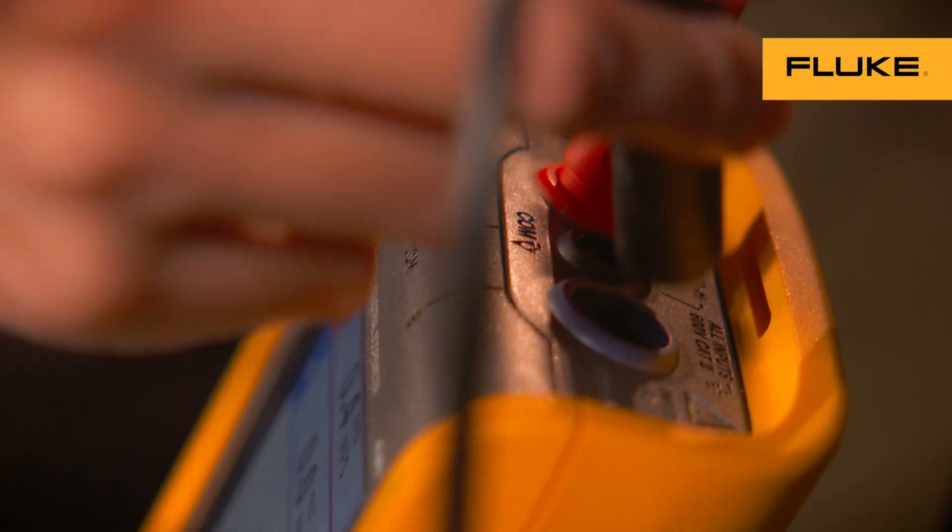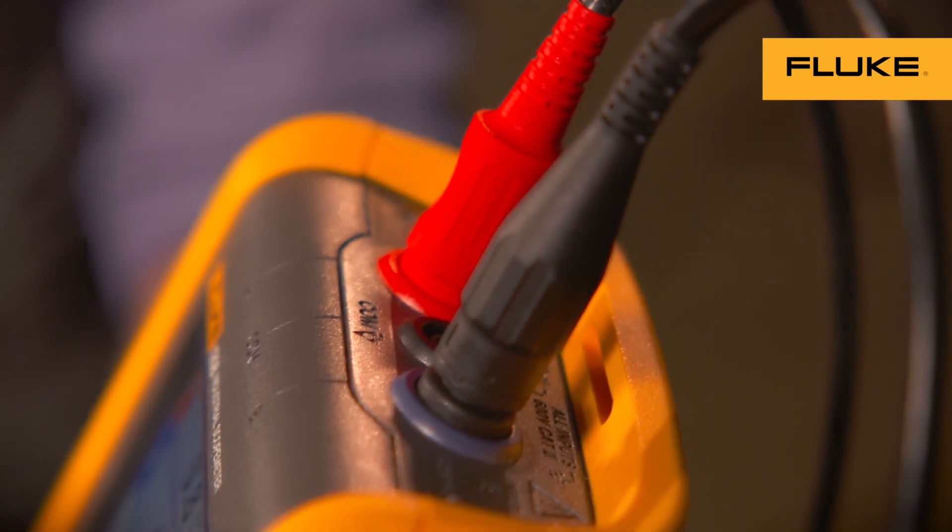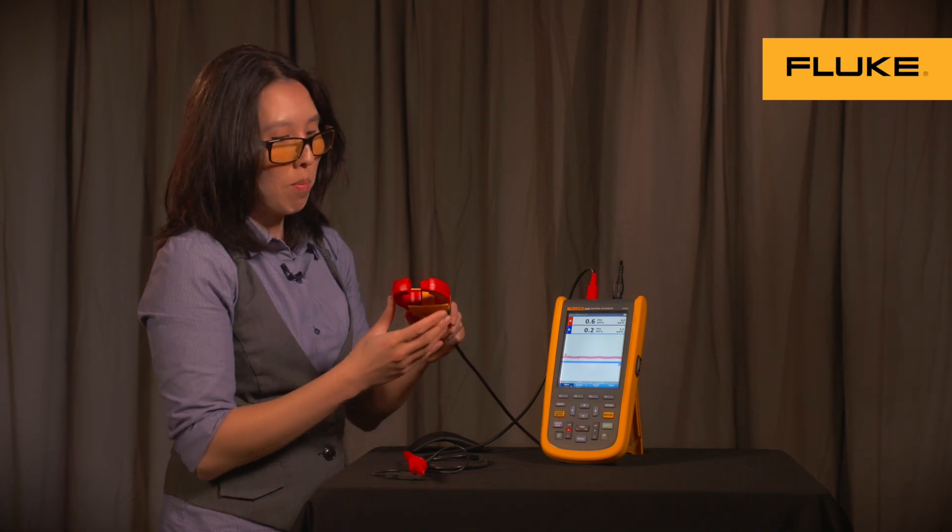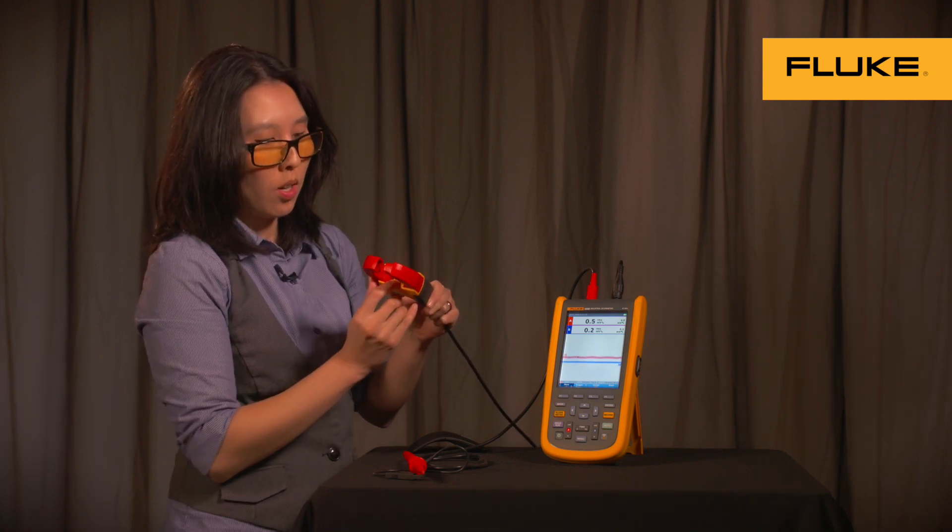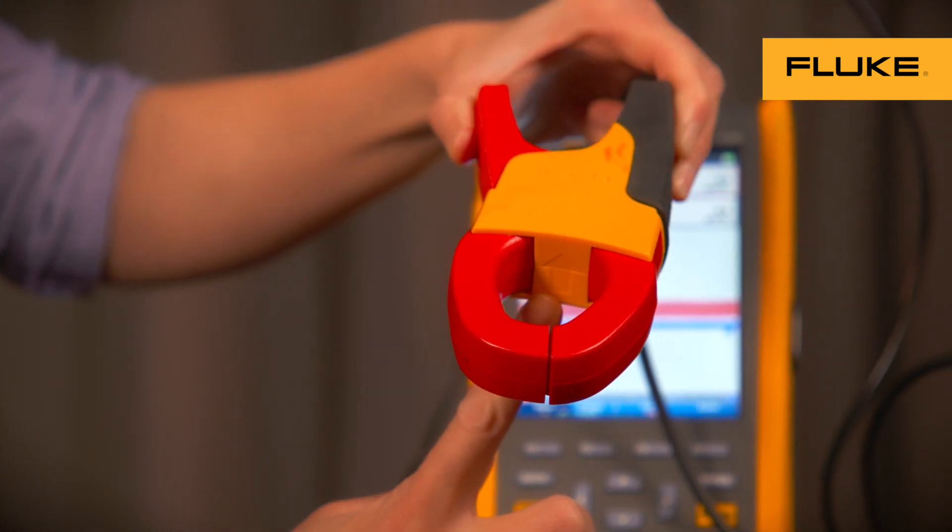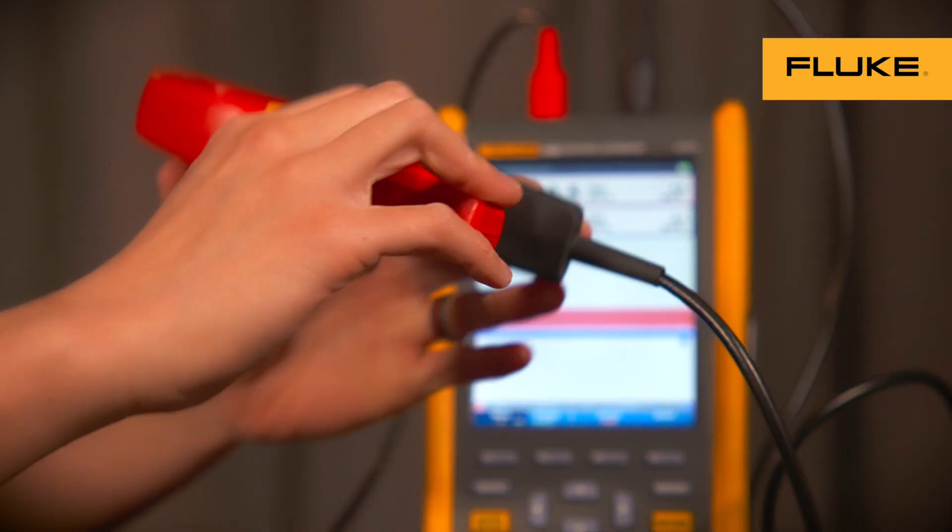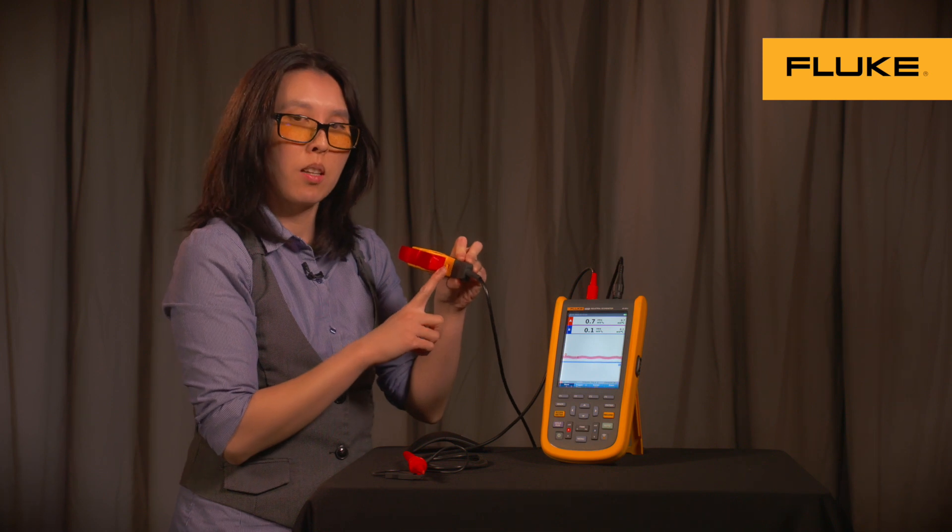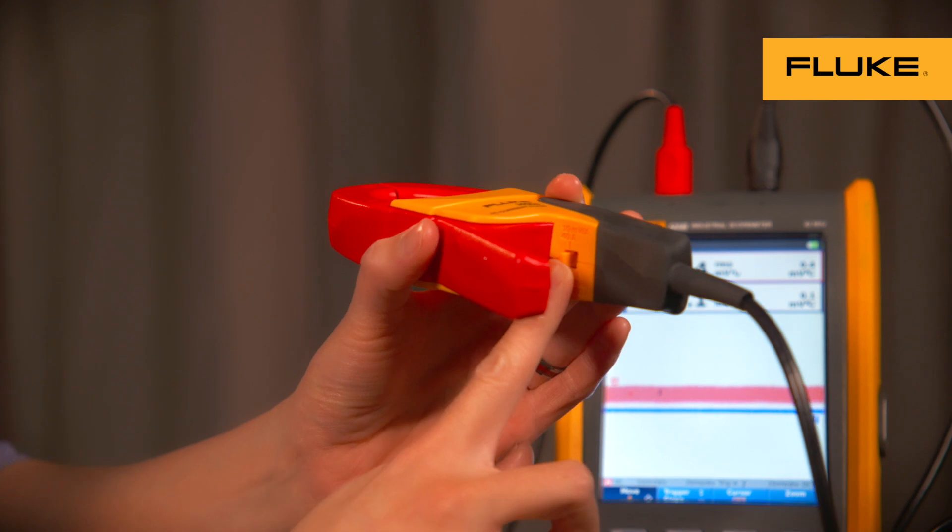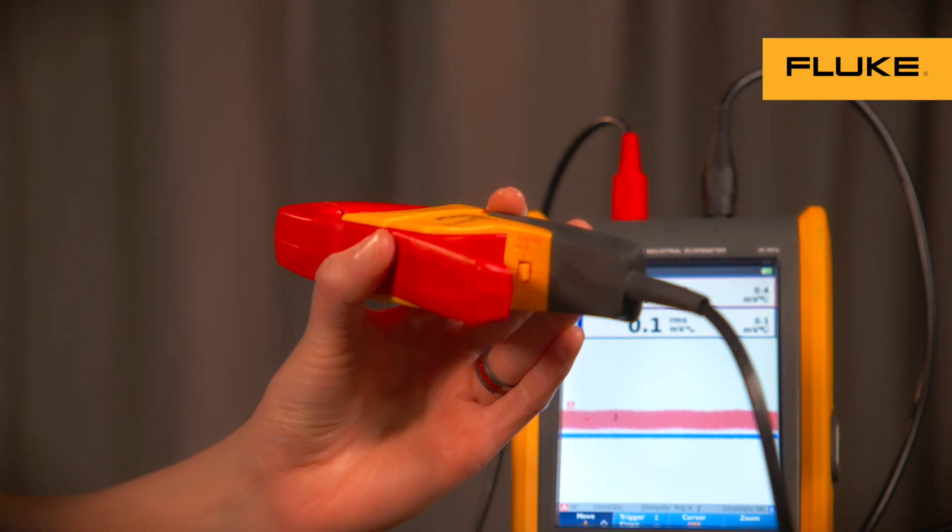Now you can hook your AC current clamp up to the instrument and clamp on to your current source. And keep in mind, when you're clamping on to the current source, this arrow right here on the inside, make sure that it's pointing towards the load. And also, you have the right sensitivity selected for your application. You can choose between 10 mV per amp or 1 mV per amp.